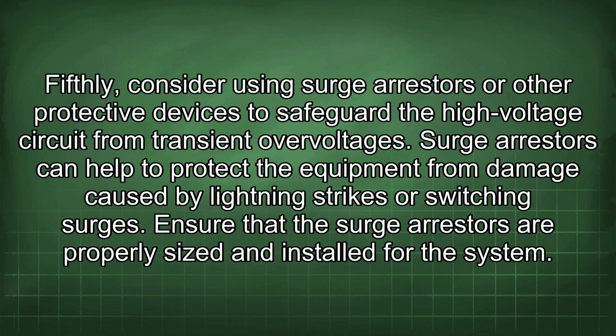Fifthly, consider using surge arresters or other protective devices to safeguard the high voltage circuit from transient overvoltages. Surge arresters can help to protect the equipment from damage caused by lightning strikes or switching surges. Ensure that the surge arresters are properly sized and installed for the system.